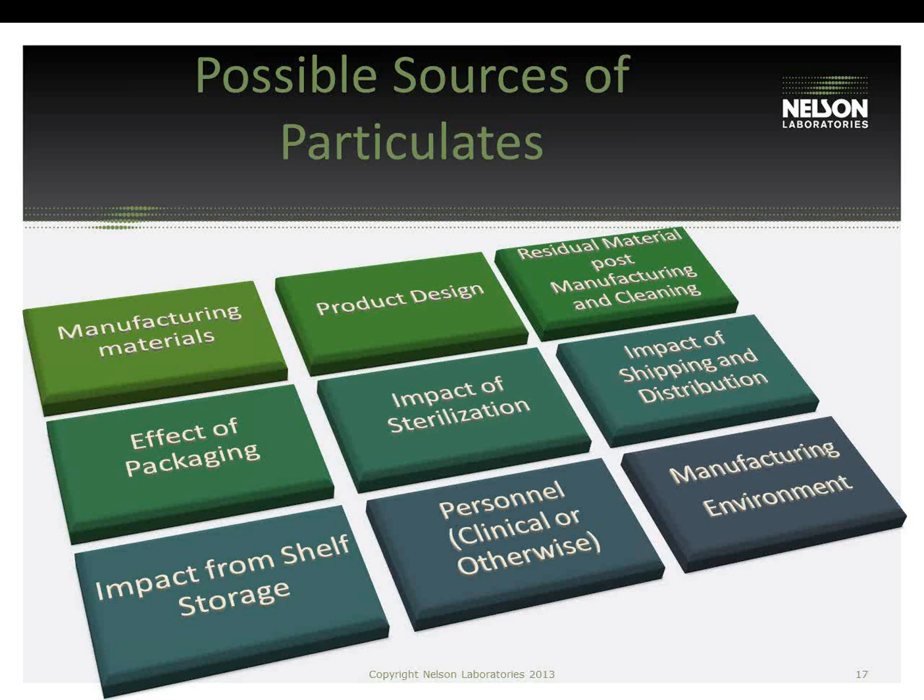As I mentioned with sterilization, shelf storage is also a large one. The regulatory like to see aged samples in testing. Shelf storage, or long periods of storage, can sometimes increase particulate matter. Not certain why that is, and it's only in some products. It's theorized that it may be due to a breakdown of compounds or possible precipitation. Not usually a big deal, but it's good to keep in mind.